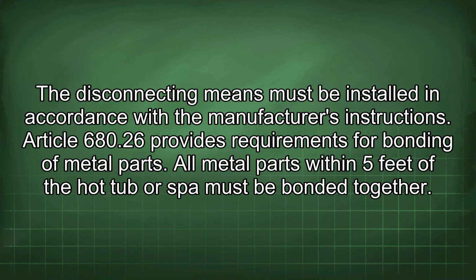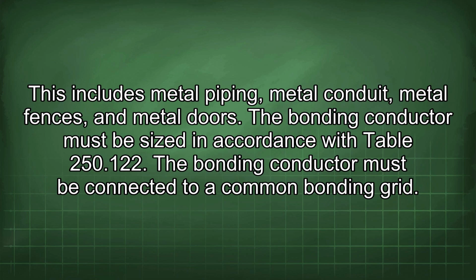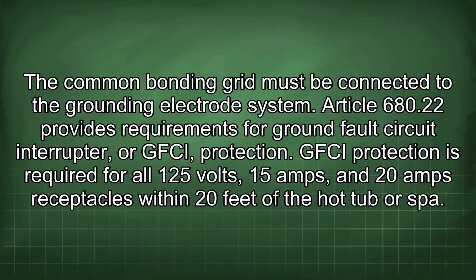Article 680.26 provides requirements for bonding of metal parts. All metal parts within 5 feet of the hot tub or spa must be bonded together. This includes metal piping, metal conduit, metal fences, and metal doors. The bonding conductor must be sized in accordance with Table 250.122. The bonding conductor must be connected to a common bonding grid. The common bonding grid must be connected to the grounding electrode system.